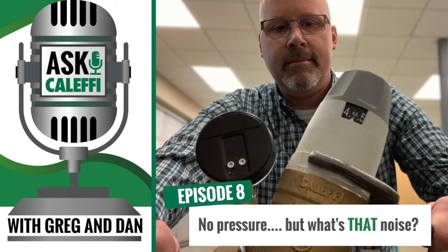So I think what you'll find is that going back, evaluating the home, finding out what the typical flow rates are, and then choosing a valve that will fit that window is what's going to work better. You may find that the half or even three quarter inch might be a better fit there. So that's the typical phone call we get about a noisy PRV or vibrations happening from a PRV. If I could count the amount of times I've had this exact conversation in real life — it happens a lot.